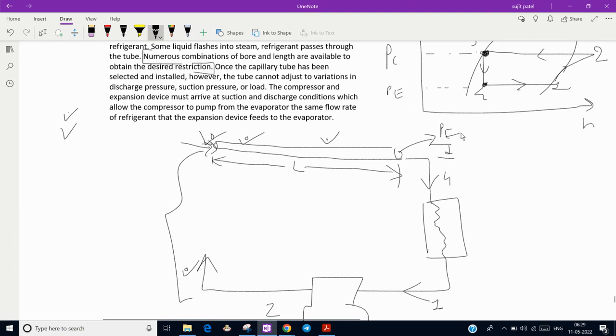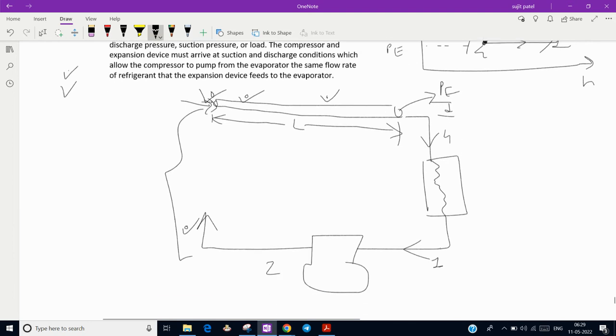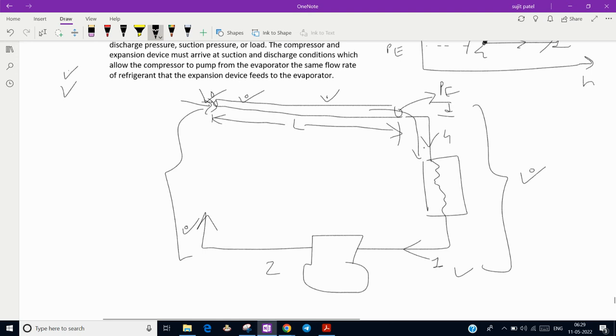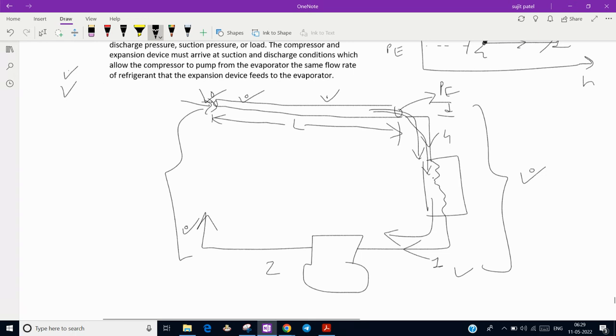The suction pressure of capillary and discharge pressure of compressor must be same, and the exit pressure of capillary and suction pressure of compressor must be same. Due to same pressure difference, whatever mass flow rate is coming from capillary to evaporator, the same mass flow rate will go to compressor. Otherwise, if more mass flow rate comes in the evaporator, then flooding will start and choking of the evaporator and less cooling capacity.